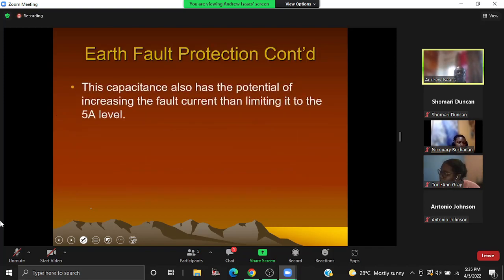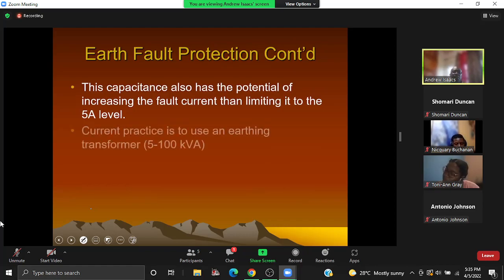Okay, and this is just continuing to speak to the use of the VT. So we're now going to focus on the method of using the earthing transformer. And we are using a transformer, and note the range that I'm putting there, which is quite significant. We're talking about 5 to 100 kVA. Now I'm going to declare my hand early. We're going to go through some calculations. It is not for you to be able to reproduce these numbers. But what I want you to focus on while I go through this are the principles that need to be considered. You don't have to worry about whether or not I can calculate this. I want you to focus on the principles being applied.